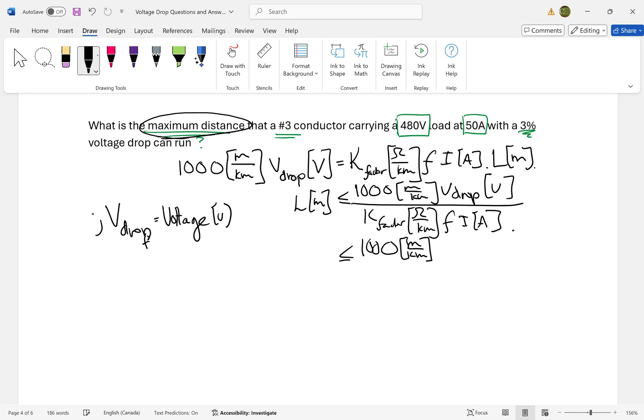That's 480 volts times 0.03 to represent the 3% voltage drop that we will accept. I can put that right in the equation: 480V × 0.03. Let's see what else needs to go in here. I also need to find the K value.